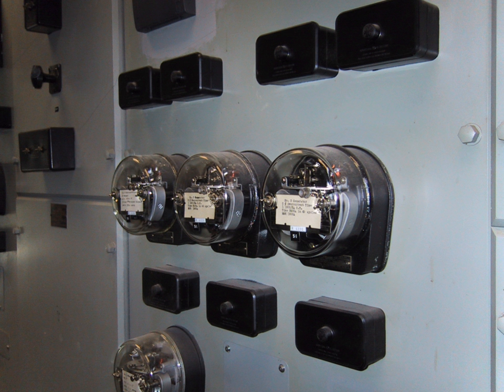In electrical engineering, a protective relay is a relay device designed to trip a circuit breaker when a fault is detected. The first protective relays were electromagnetic devices, relying on coils operating on moving parts to provide detection of abnormal operating conditions such as overcurrent, overvoltage, reverse power flow, overfrequency, and underfrequency.